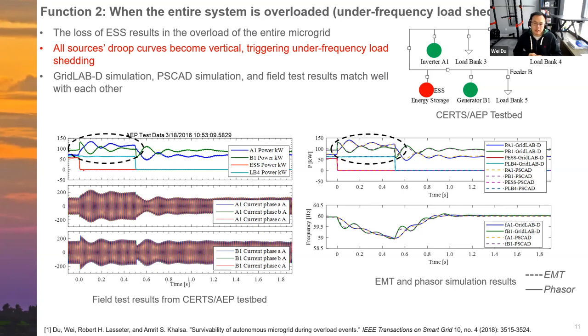So for this case, we have three sources: grid forming inverter A1, the synchronous generator B1, and the energy storage. And we treat this energy storage as a contingency. So this results in the overload of both grid forming inverter A1 and the synchronous machine B1. Both A1 and B1 are equipped with this Pmax controller. So when this overload happens, the Pmax controllers for both A1 and B1 are activated. That means their droop curves all become vertical. That means when both A1 and B1 are overloaded, both of them reduce their frequency.